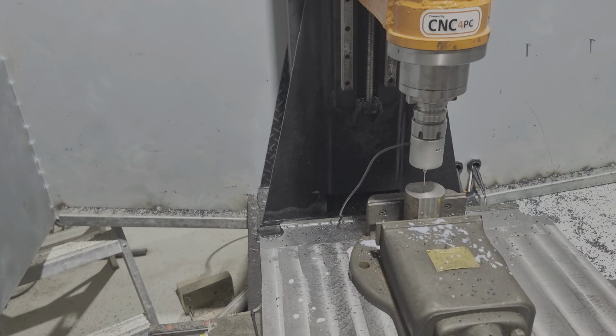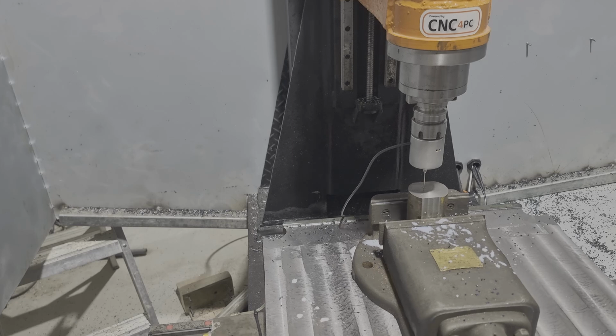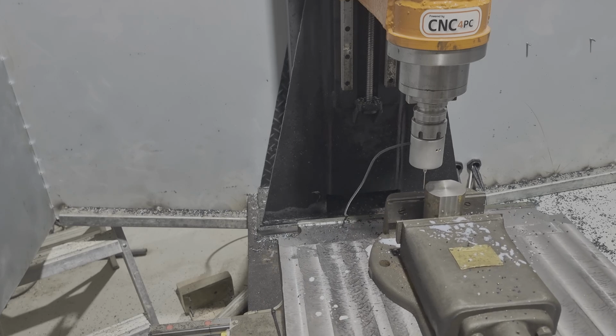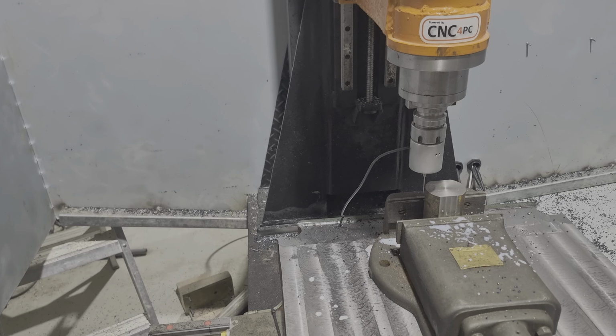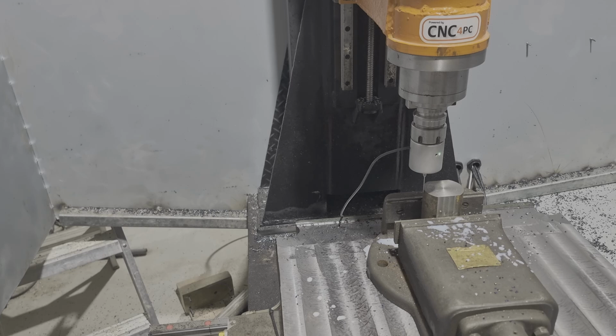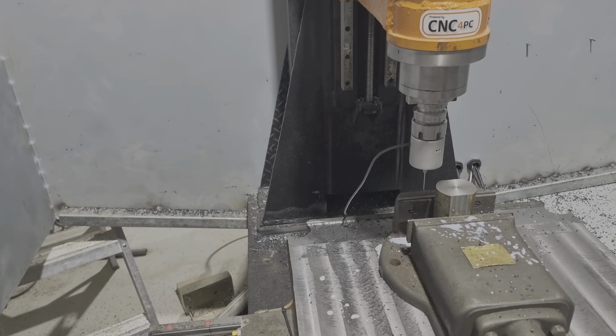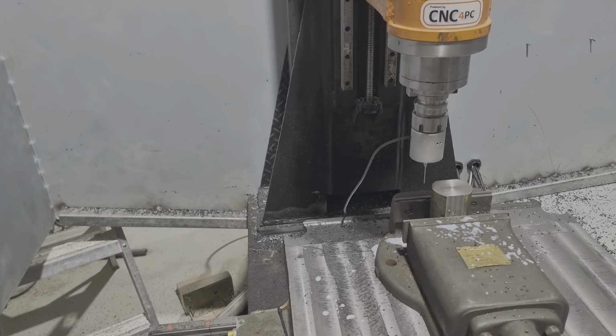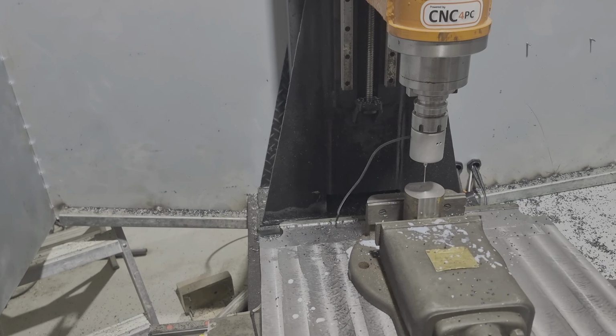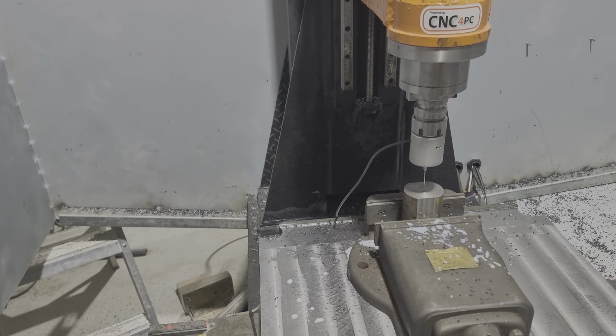So yeah, lined it up with that, and then moved it over and dropped it down. And then you'll see the little green light go off again when I press the button, and you see the table moving. The green light there, so that's set X0 and Y0, and then I just bring it across and drop it down onto Z. Once the Z height's set, that's basically it for setting up the part. The probe makes it so much easier to do.